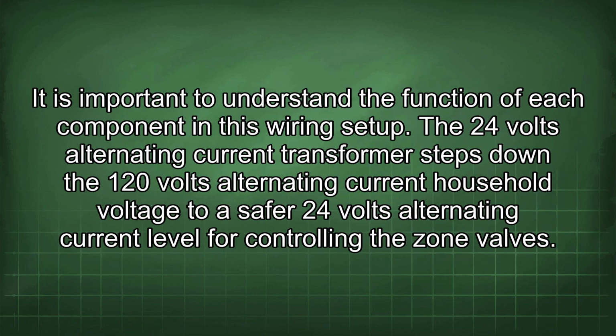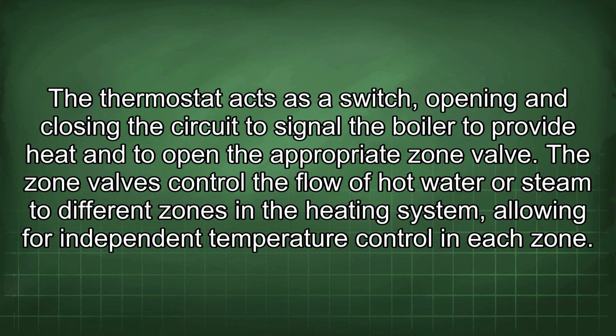It is important to understand the function of each component in this wiring setup. The 24 volts alternating current transformer steps down the 120 volts alternating current household voltage to a safer 24 volts alternating current level for controlling the zone valves. The thermostat acts as a switch, opening and closing the circuit to signal the boiler to provide heat and to open the appropriate zone valve.